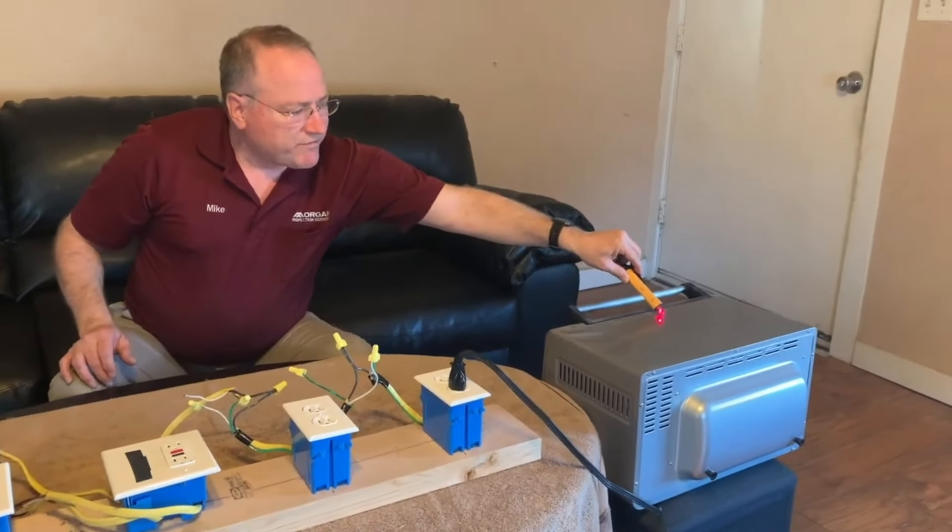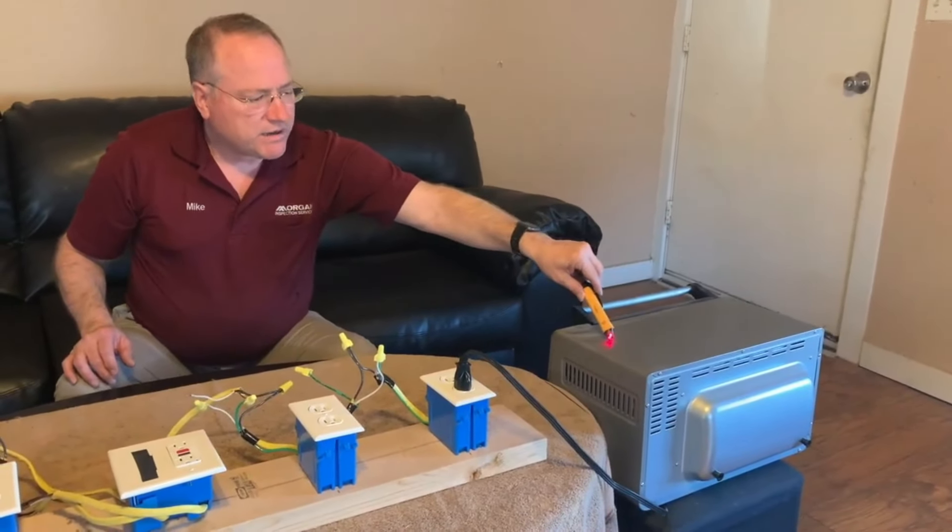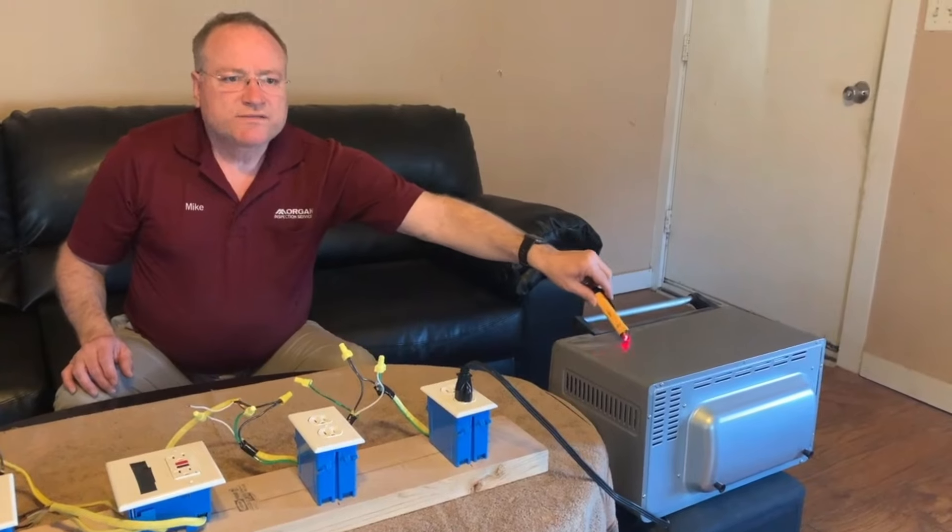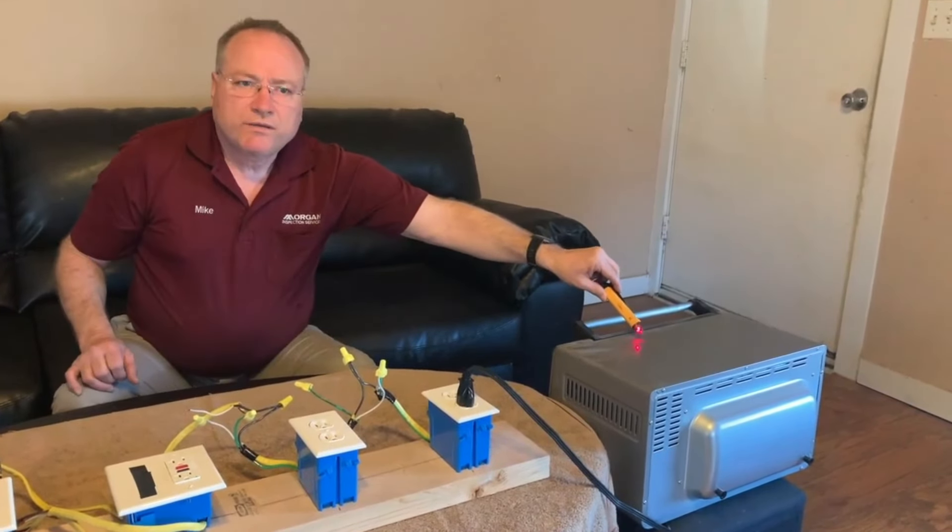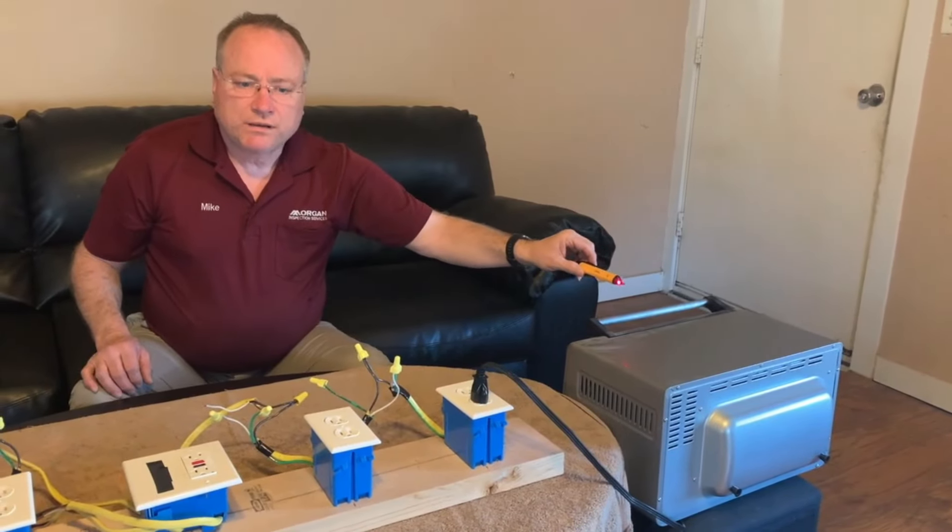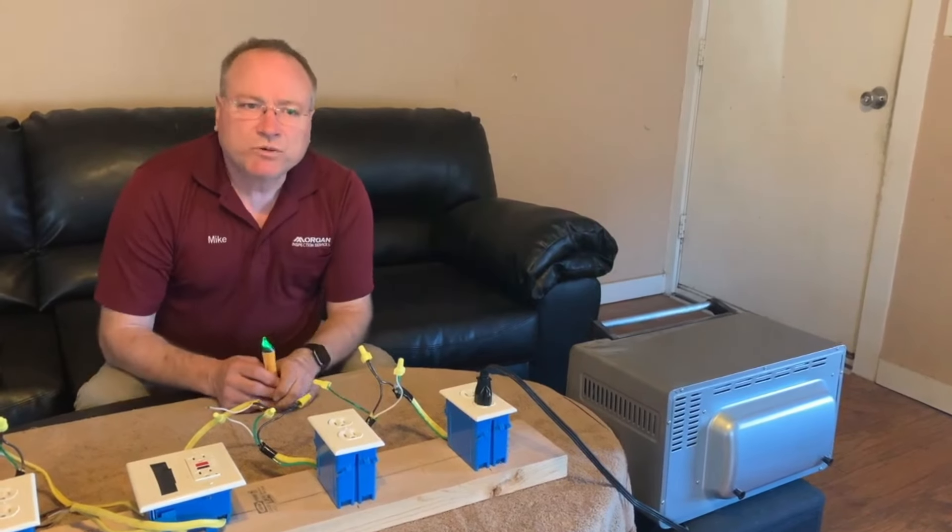And with my voltage detector, let me show you what we've got. The shell or the frame of this toaster oven is live. It's got 120 volts. If someone were to walk up to this and touch it, they could easily be electrocuted. That's the danger of bootleg grounds.